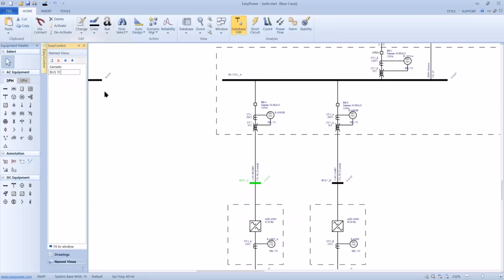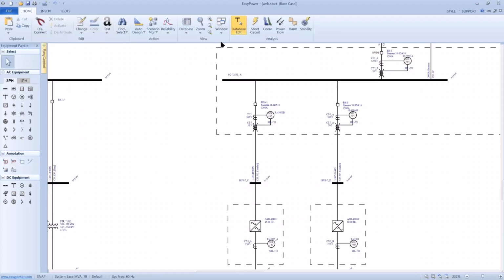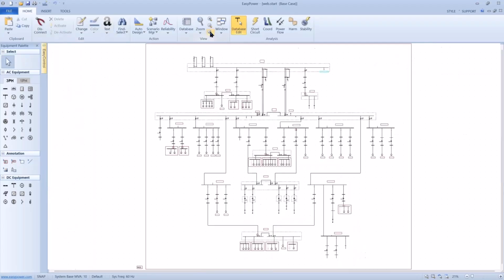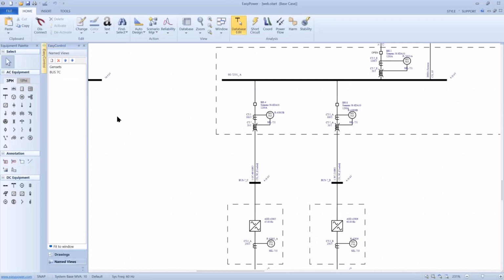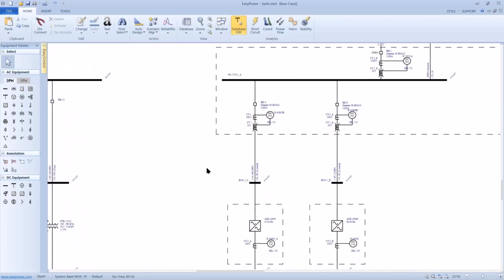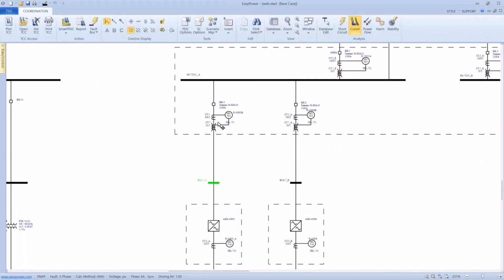And you'll see why that helps here in a minute. What it allows me to do is jump back and forth from any reference point that I want to start with, without a whole lot of scanning and scrolling around. So here's bus 7C. I want to go into coordination. First thing I want to do is a sequence of events report for bus 7C. So I've isolated on the bus, go into coordination, fault the bus.